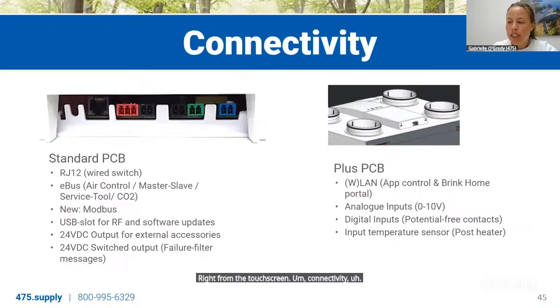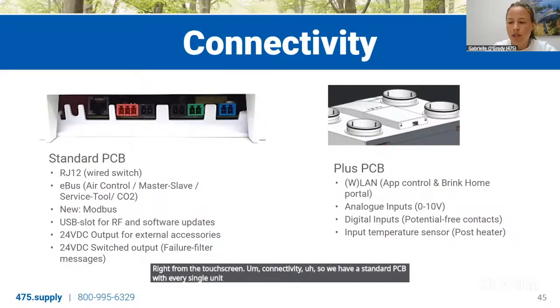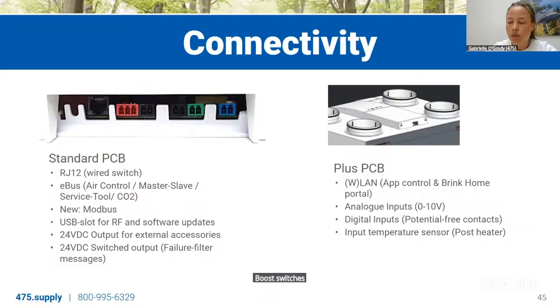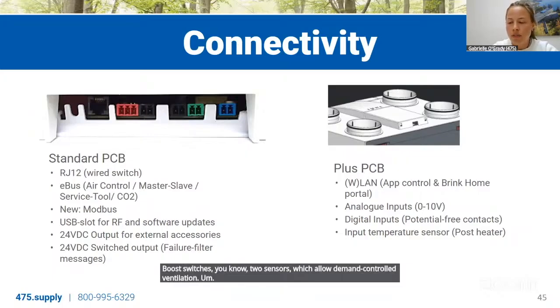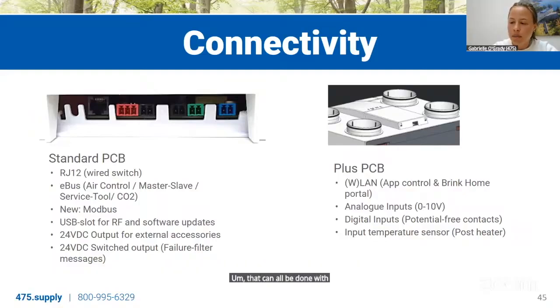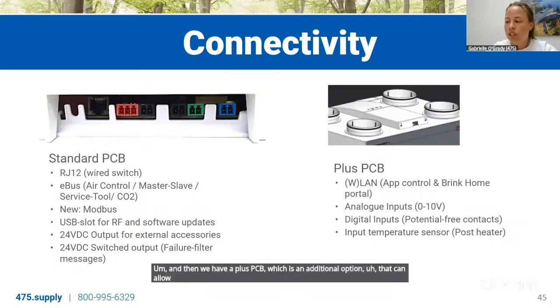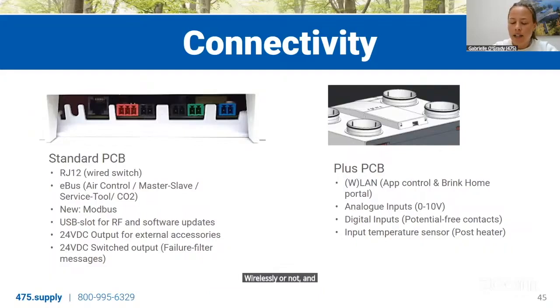Connectivity, so we have a standard PCB with every single unit that allows you to connect to a lot of our controls, including boost switches, CO2 sensors, which allow demand-controlled ventilation, and an RH sensor if you want RH-triggered boosting. That can all be done with the standard PCB. It's also Modbus capable. And then we have a plus PCB, which is an additional option that allows additional sophistication by allowing you to connect to the internet, wirelessly or not, and connect to other building automation systems as well.